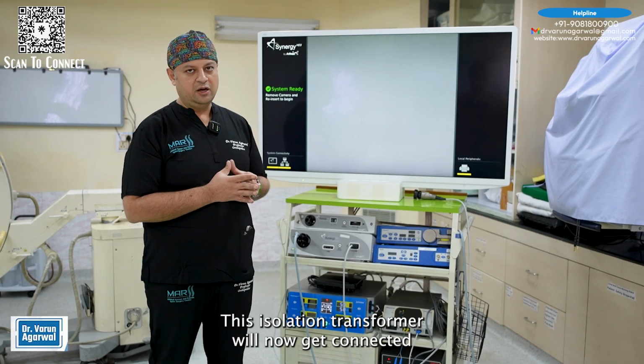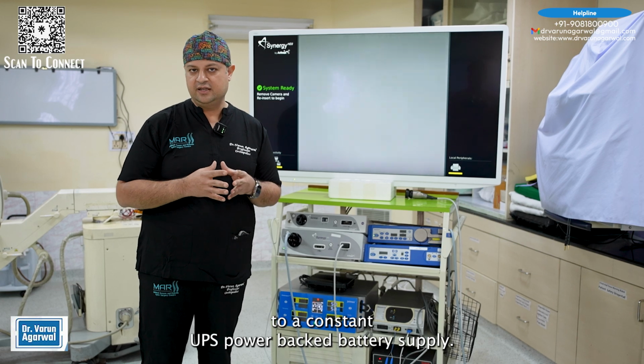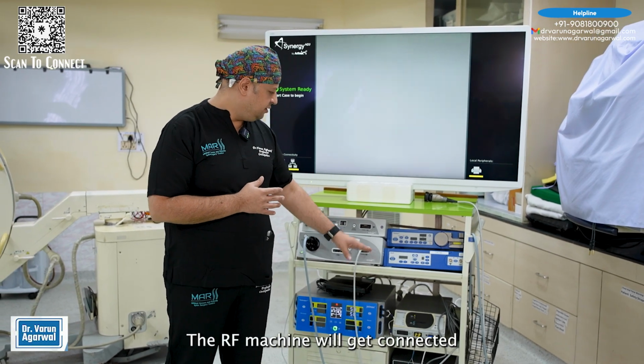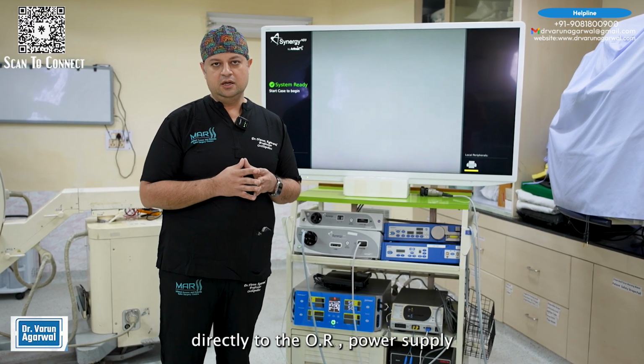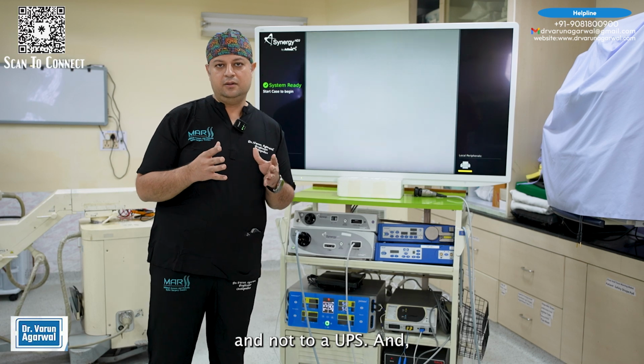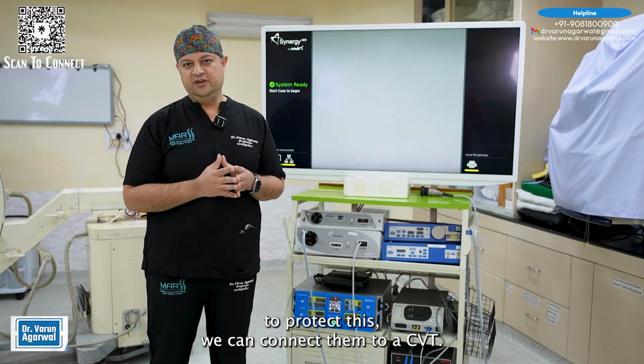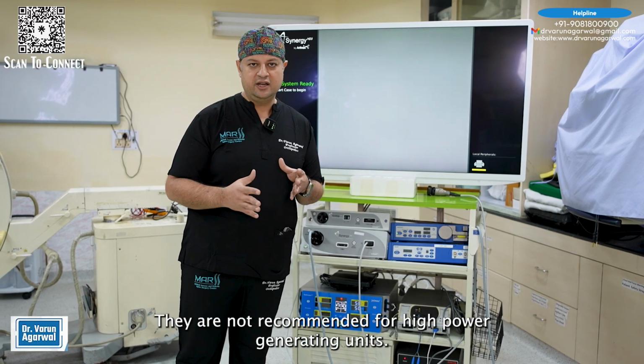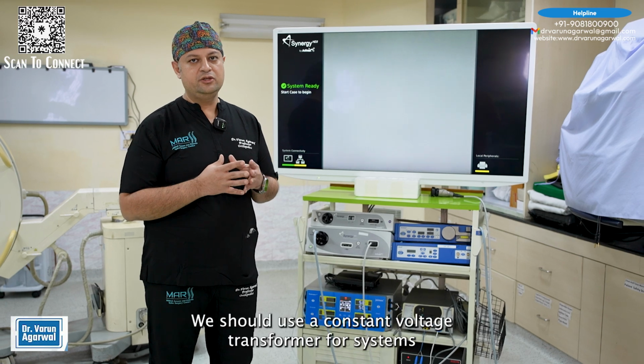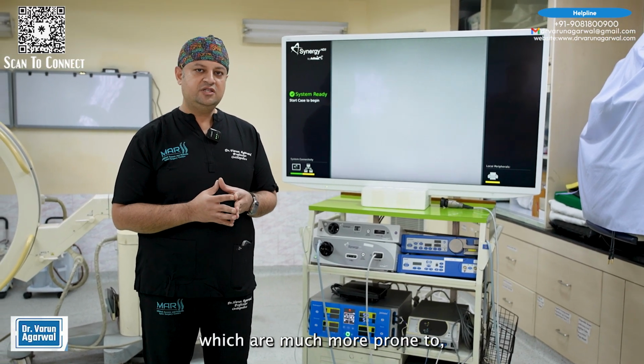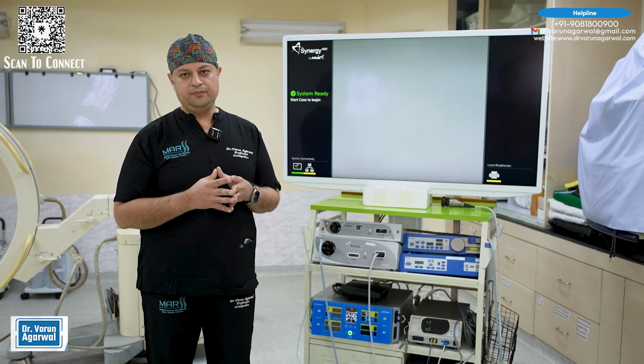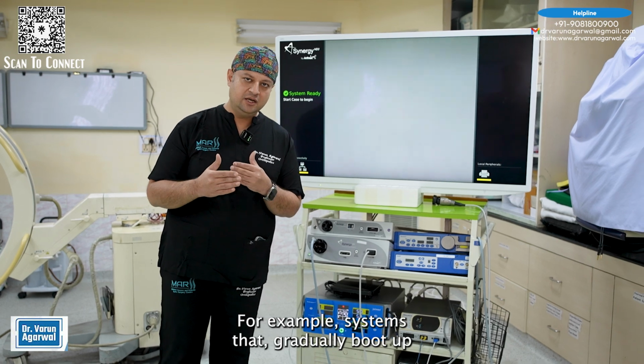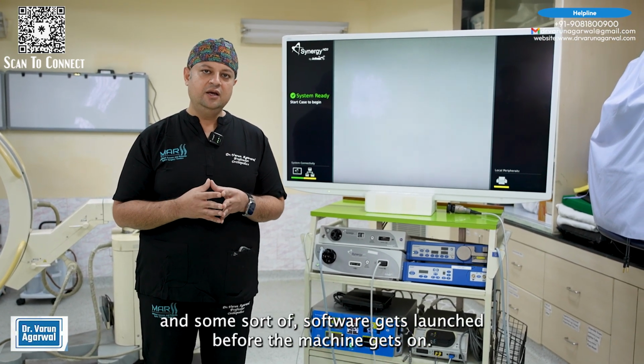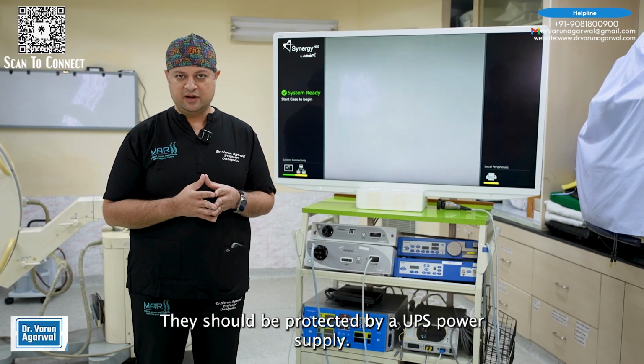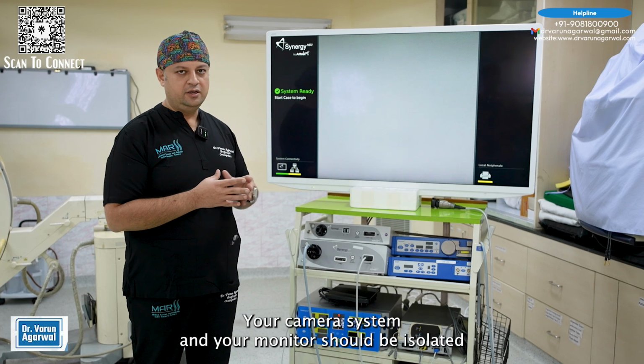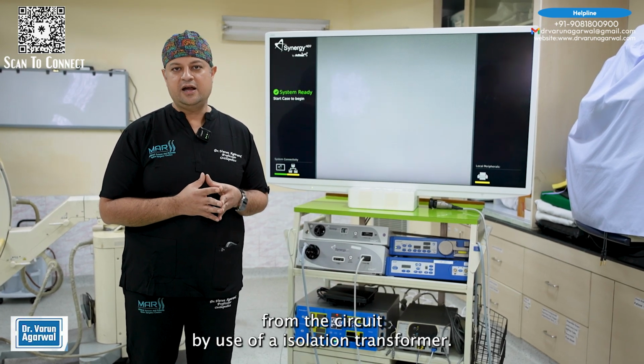This isolation transformer will then get connected to a constant UPS power-backed battery supply. The RF machine will get connected directly to the OR power supply and not to a UPS, and to protect it we can connect it to a CVT. Stabilizers we don't use in the clinical setting; they are not recommended. For high power generating units we should use a constant voltage transformer. Systems which are much more prone to break down if they are suddenly switched off, for example systems that gradually boot up and launch some software before the machine comes on, should be protected by a UPS power supply. Your camera system and your monitor should be isolated from the circuit by use of an isolation transformer.